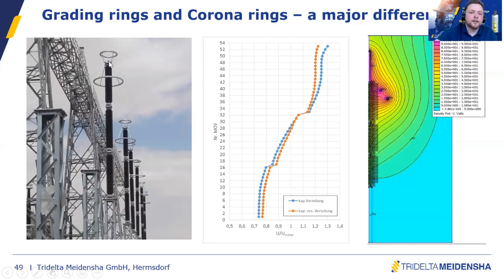Okay, and secondly, don't mix it up. We have the grading ring hanging down on the surge arrestor. We have a very classic installation here. This is providing a so-called grading performance. The surge arrestor has a specific length and a voltage on top. And the zinc oxide blocks have a capacitance from top to the bottom, but they also have a capacitance from top to the sides. So that's what's called stray capacities in electrical engineering.